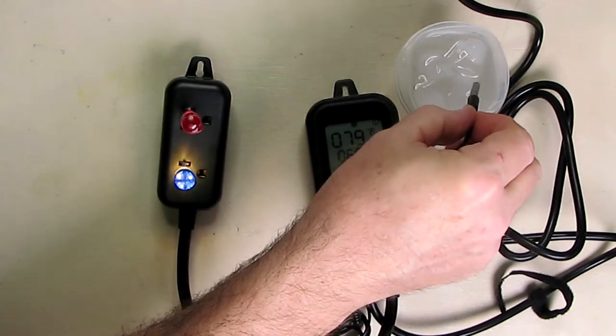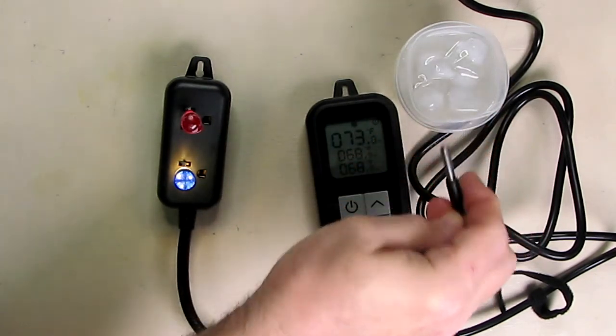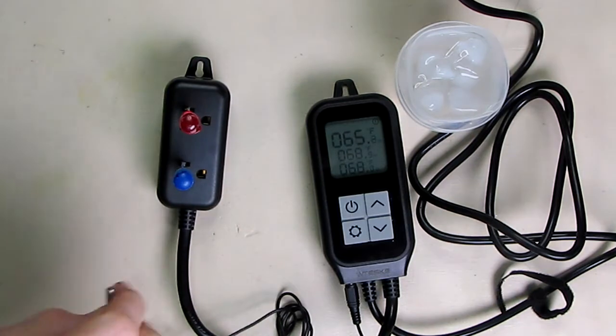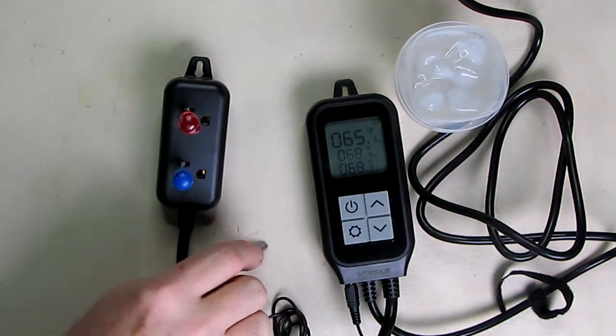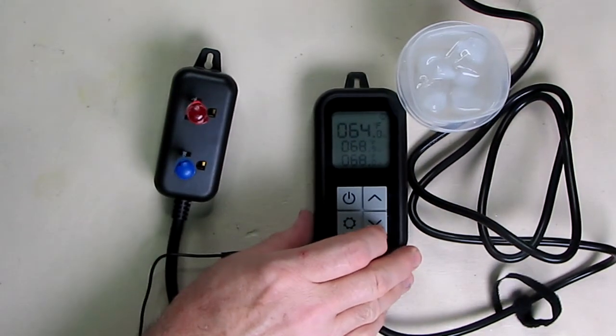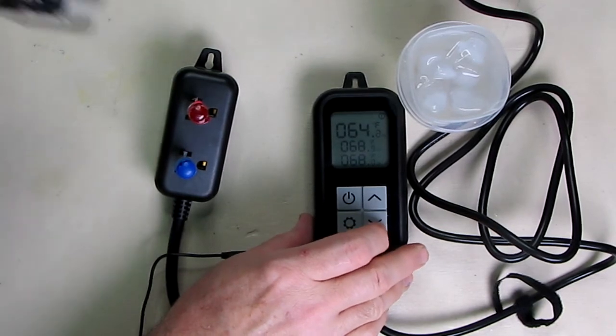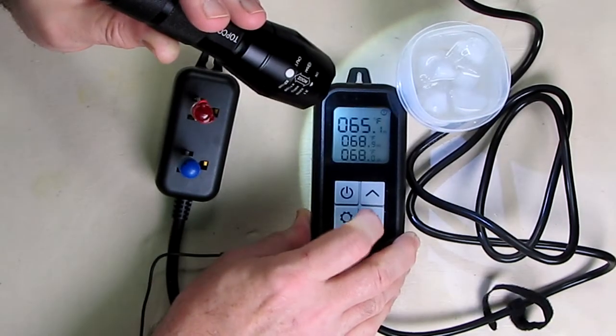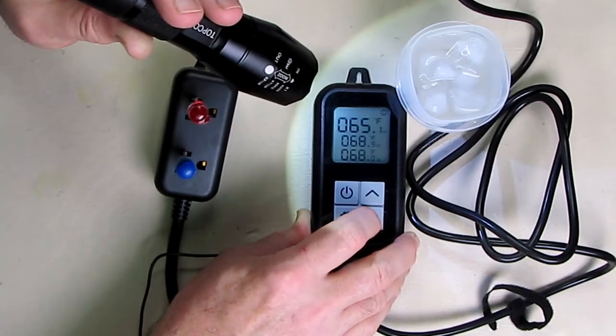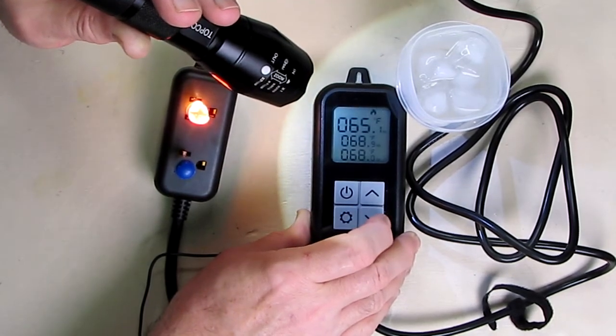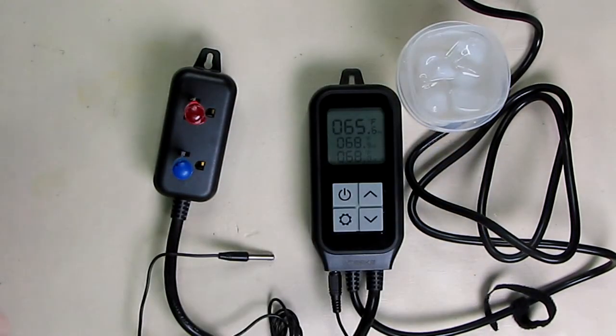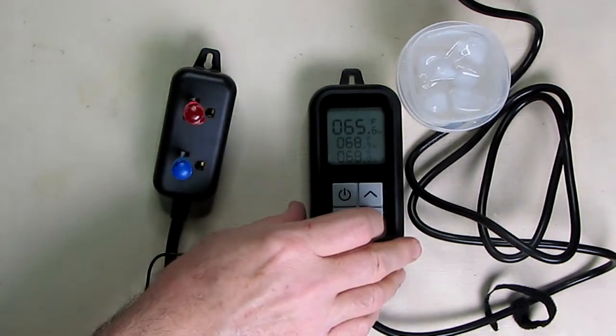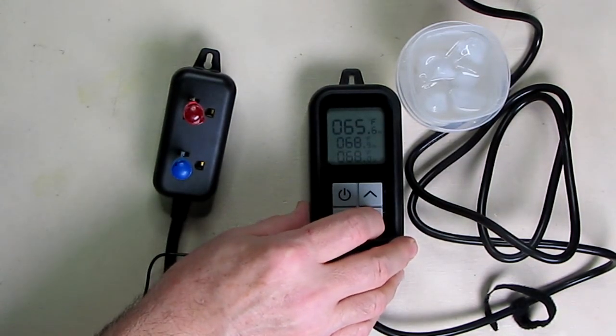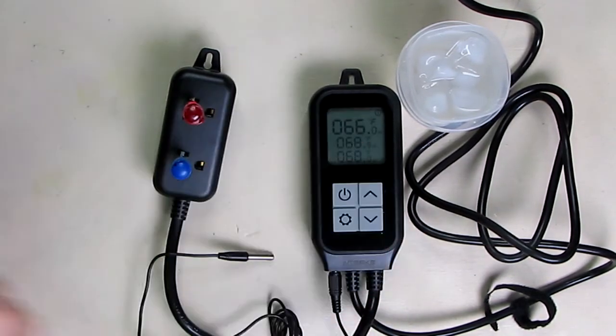And so let's put the probe back in the ice right there, and then look what happened. It shut off, and the alarm shut off. You could also turn this alarm off by hitting the down button right here. I'm sorry, you hold it for 3 seconds, and that'll turn the alarm off. So if you don't want to have that alarm, you could turn it off that way. You want to turn it back on, you just hold that down, and the alarm goes back on.